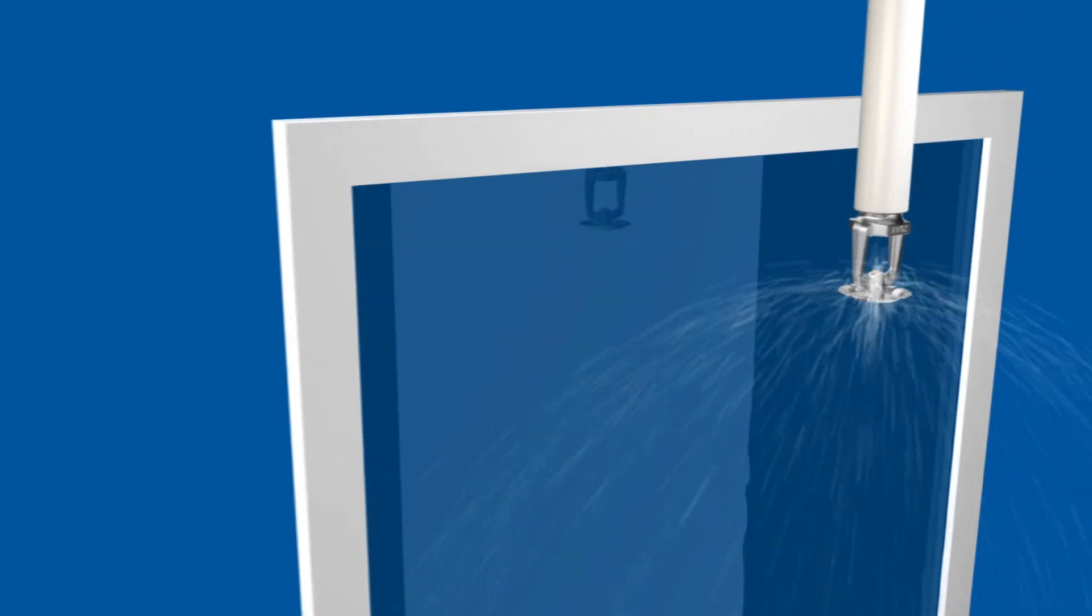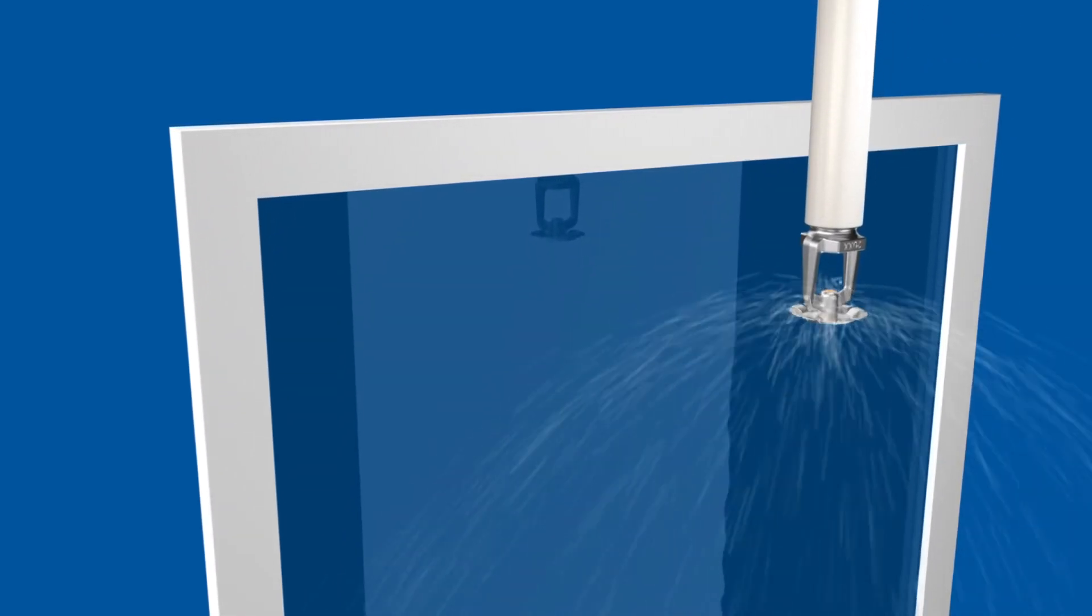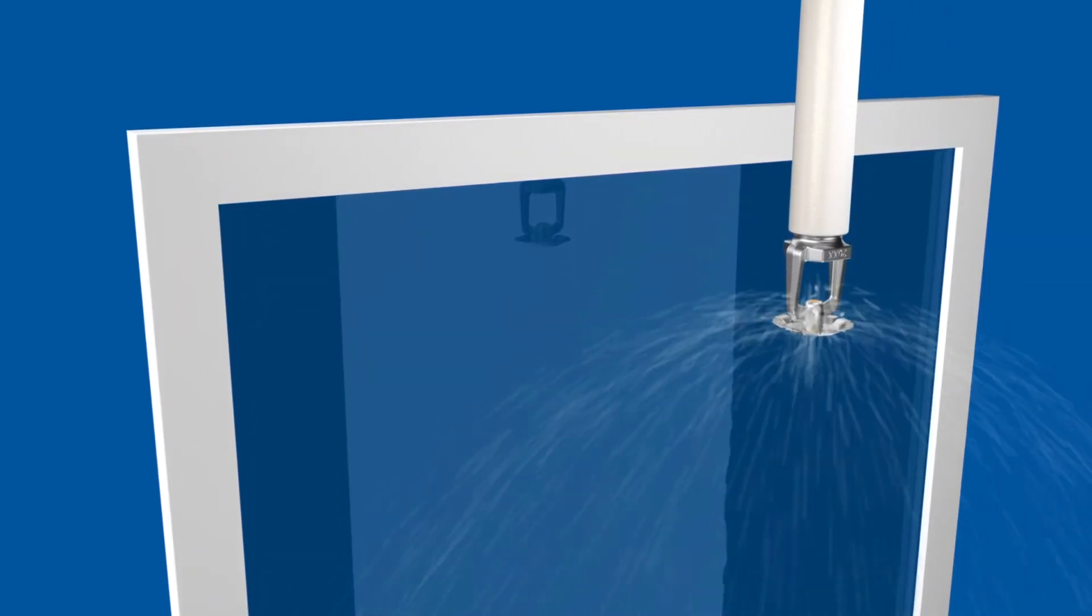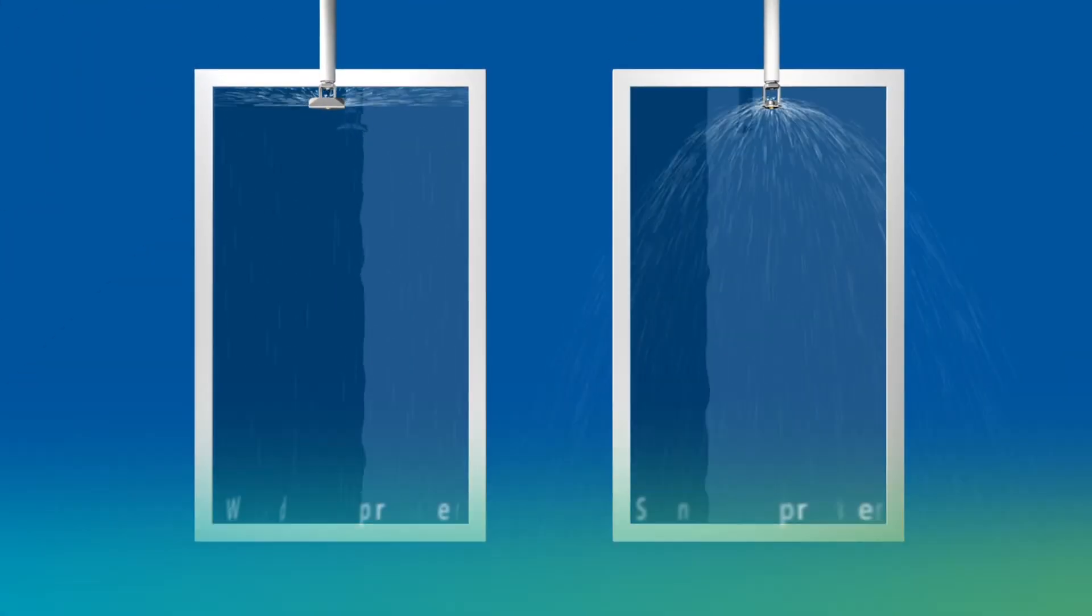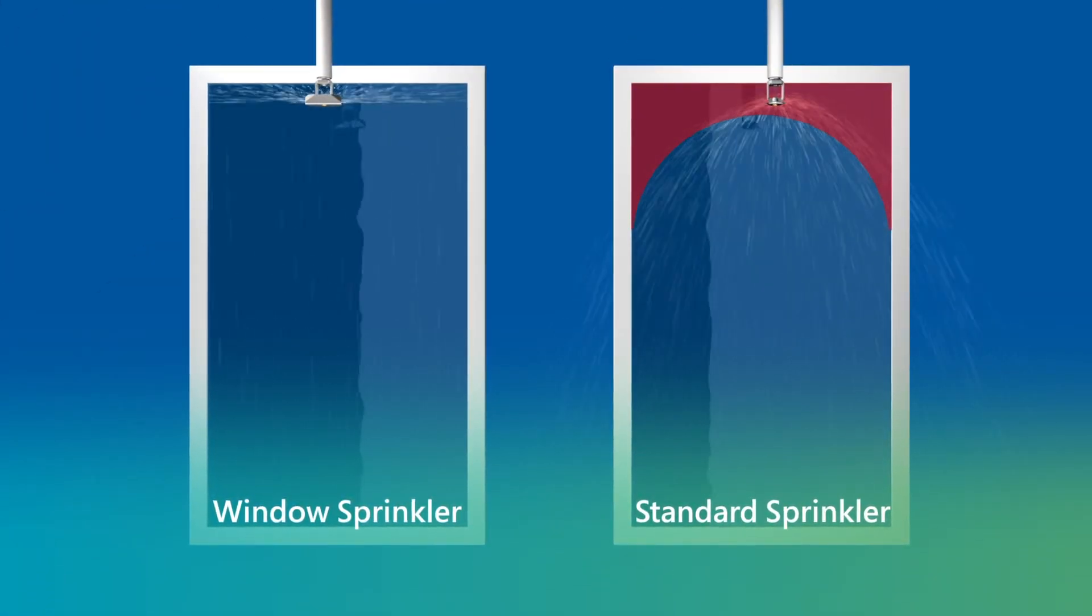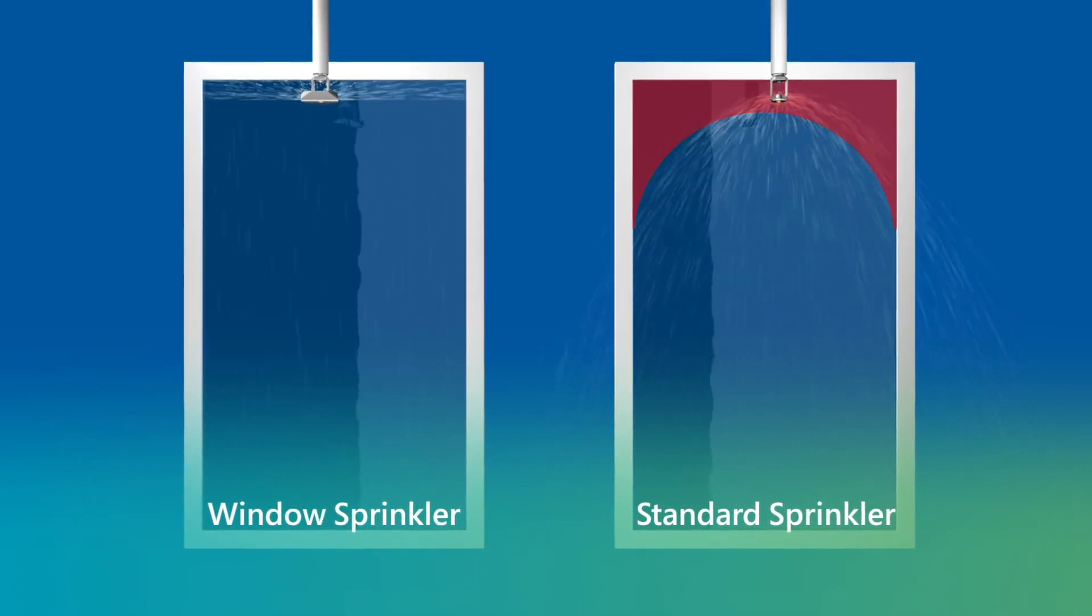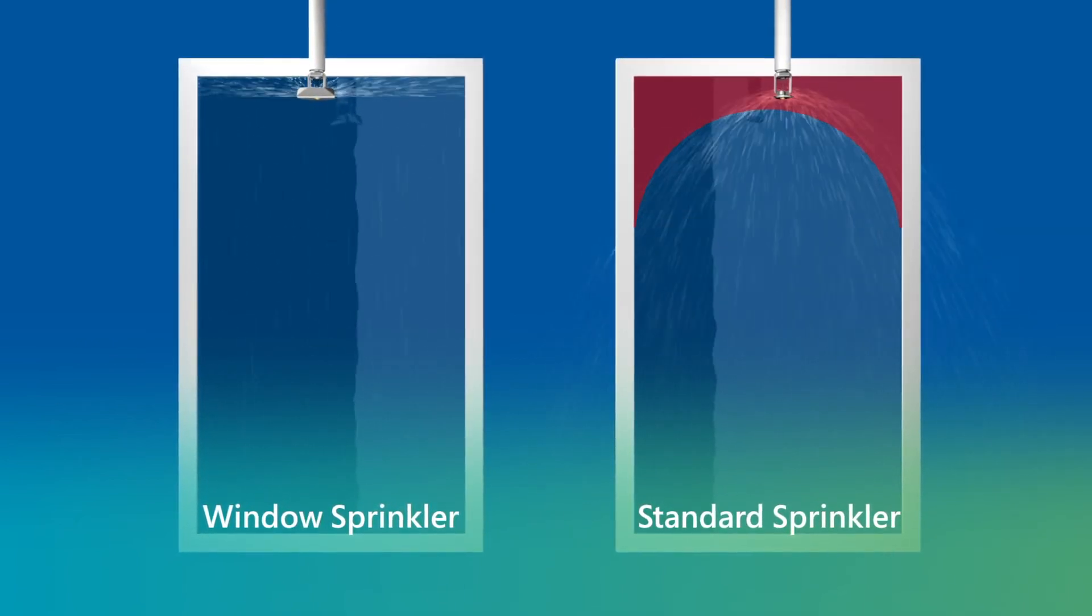Standard sprinklers, on the other hand, are designed to protect floors and wall areas. While they may wet windows, they are not designed to spray an even coat of water. This means they cannot provide protection equivalent to that of a two-hour fire rated wall assembly, whereas a window sprinkler is designed to do just that.